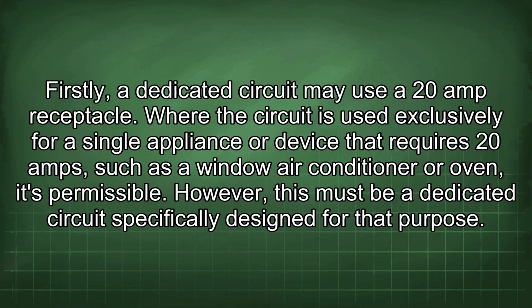Firstly, a dedicated circuit may use a 20 amp receptacle. Where the circuit is used exclusively for a single appliance or device that requires 20 amps, such as a window air conditioner or oven, it's permissible. However, this must be a dedicated circuit specifically designed for that purpose.